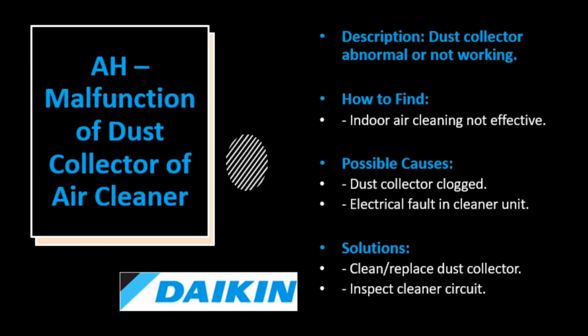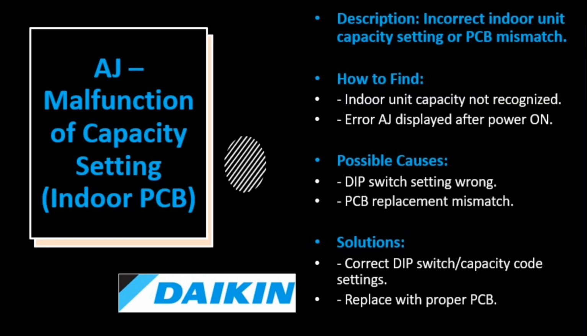AH is for dust collector issues. Clean or replace the collector and check the cleaner circuit. And finally, AJ is capacity setting malfunction. Double-check your DIP switch and capacity code settings, and make sure you're using the right PCB.